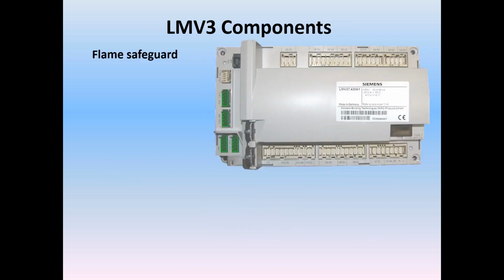LMV3, as you see it, is the flame safeguard. It comes in an LMV37, which is a single fuel unit, with all those features that we talked about. The LMV36 looks identical. It has all the features of the LMV37, only it has two fuel curves in it so that you can run a gas curve and you can run an oil curve. The other difference is that the LMV36 does not have the revert to pilot feature. So LMV37 has revert to pilot, single fuel. LMV36 is dual fuel and does not have the option for revert to pilot.